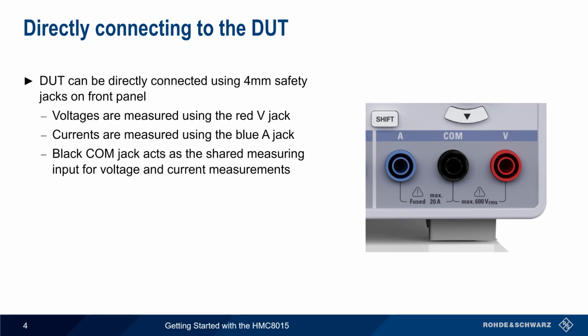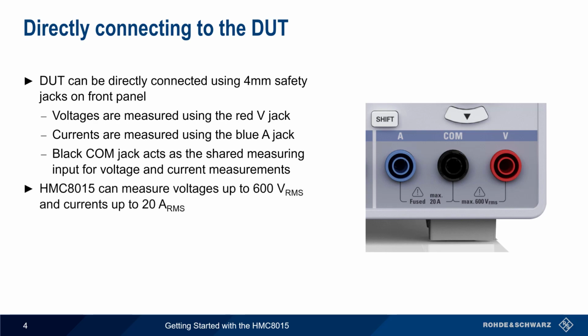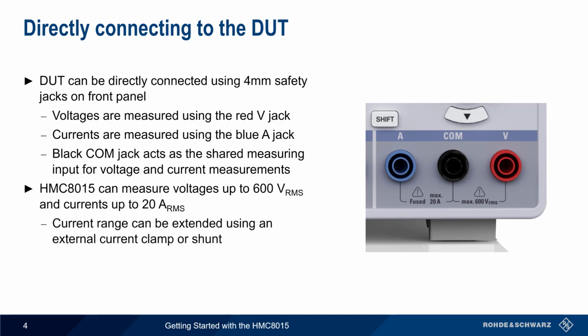As indicated on the front panel, the HMC can measure up to 600 volts RMS and 20 amperes RMS, although the current range can be significantly extended using an external current clamp or shunt. Note that for safety purposes and to avoid instrument damage, the HMC will automatically shut down if these limits are exceeded.